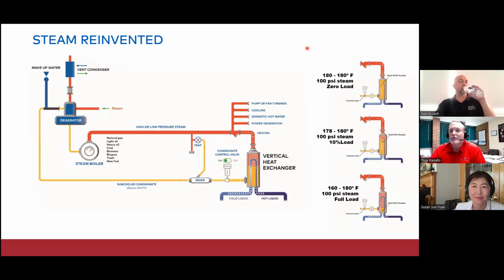We call this steam reinvented. So when you look at this system, the left-hand side over here looks pretty much the same as we saw in the previous slide. But now we've eliminated a lot of infrastructure here because we can take high pressure steam directly into our vertical flooded heat exchanger. We do not control on the steam side. We control on the condensate side. That's this condensate control valve right here.